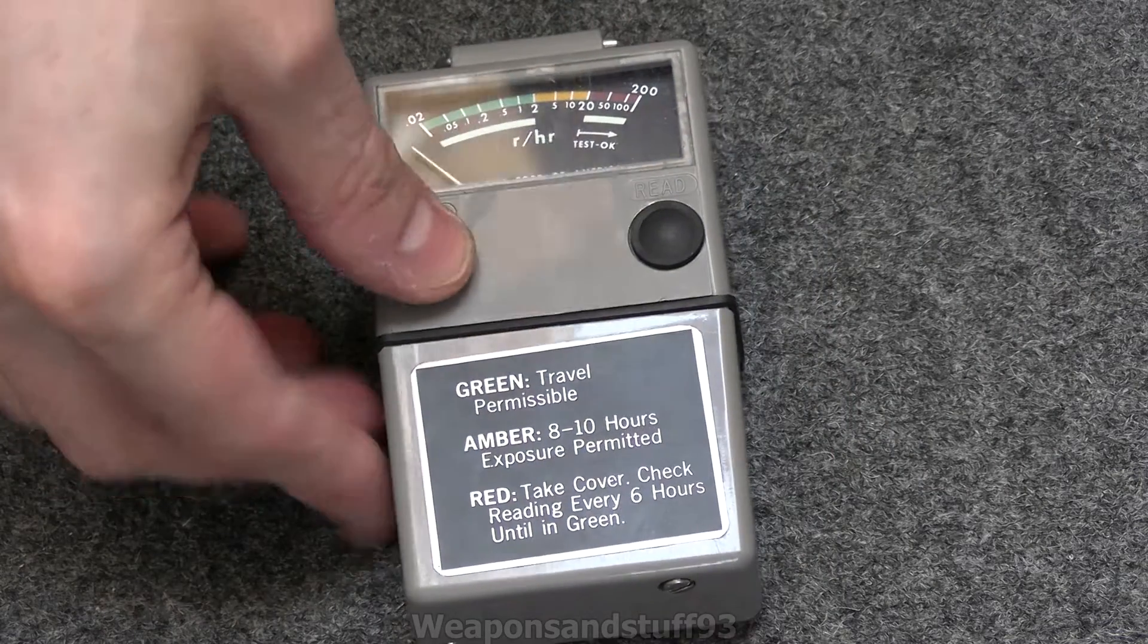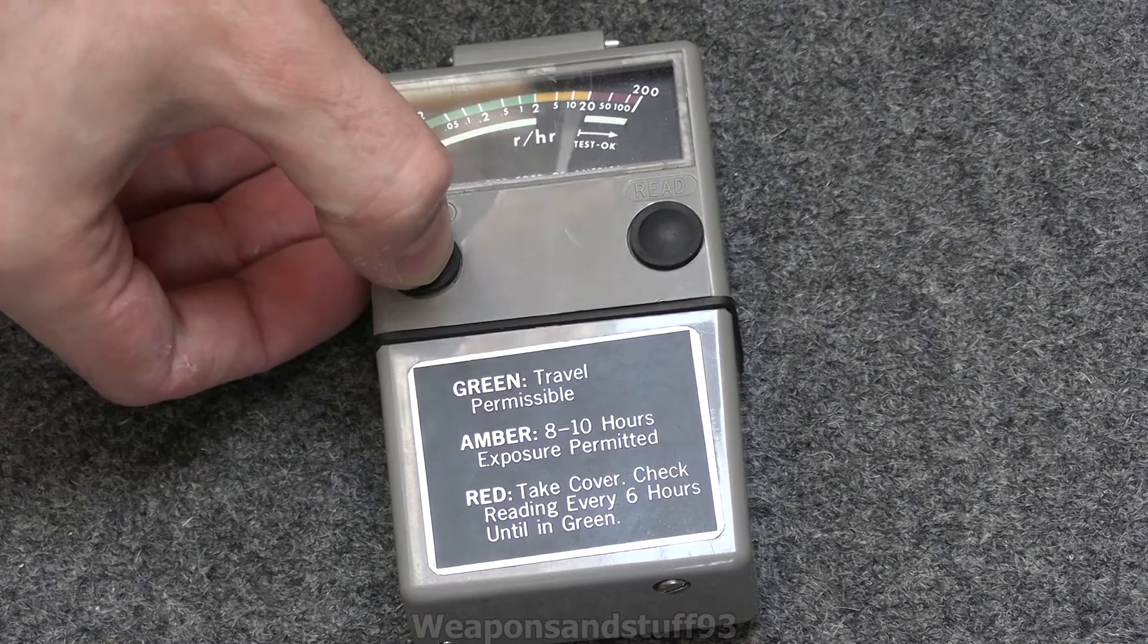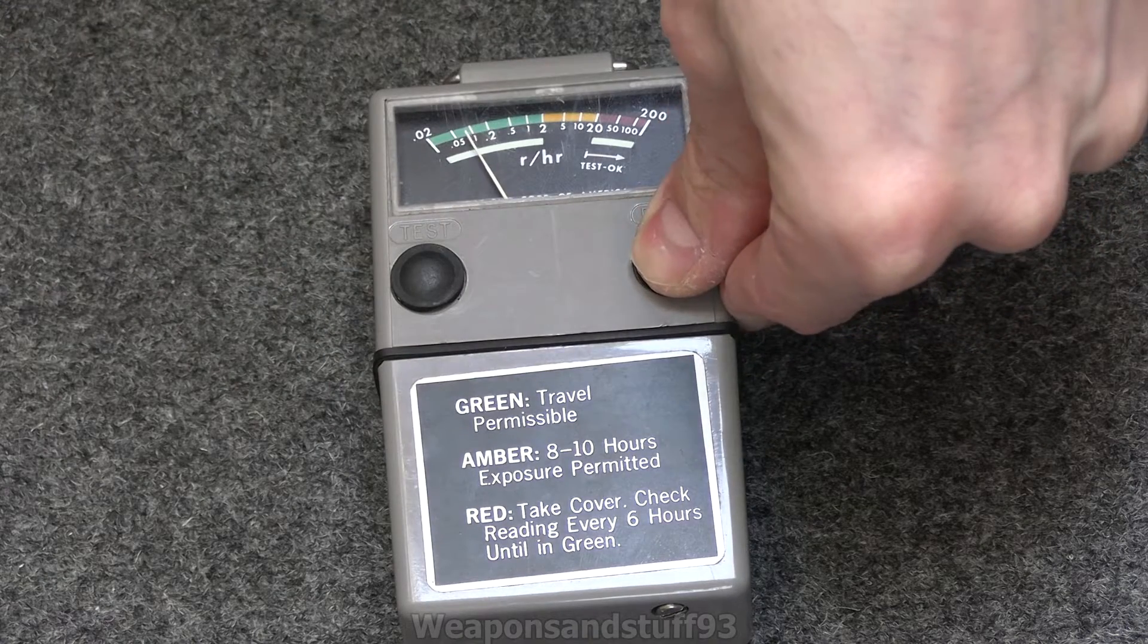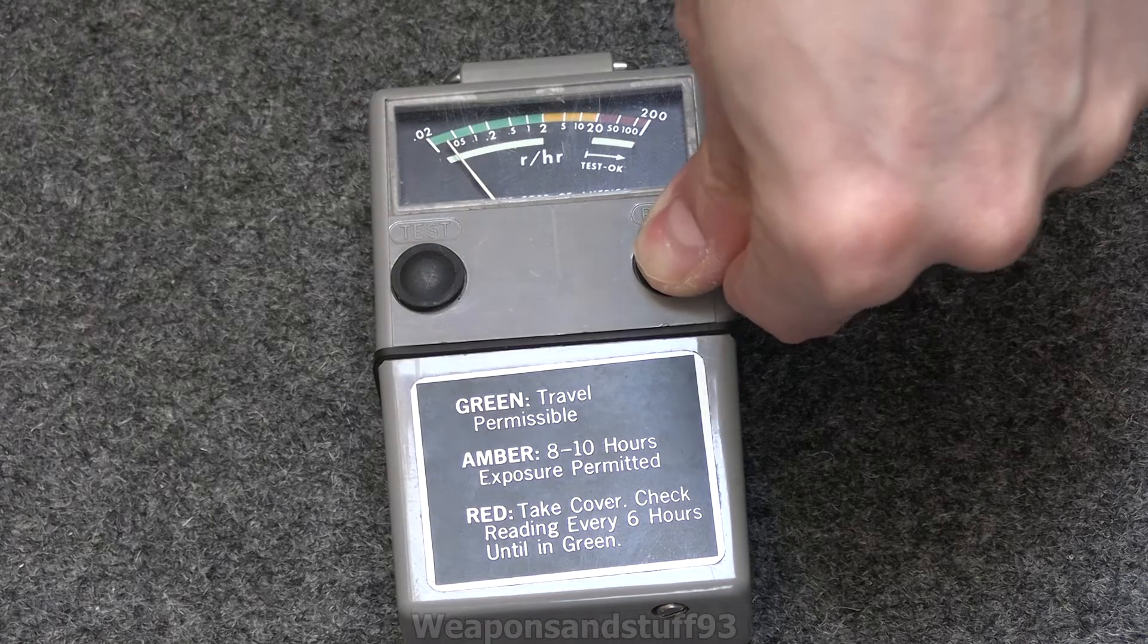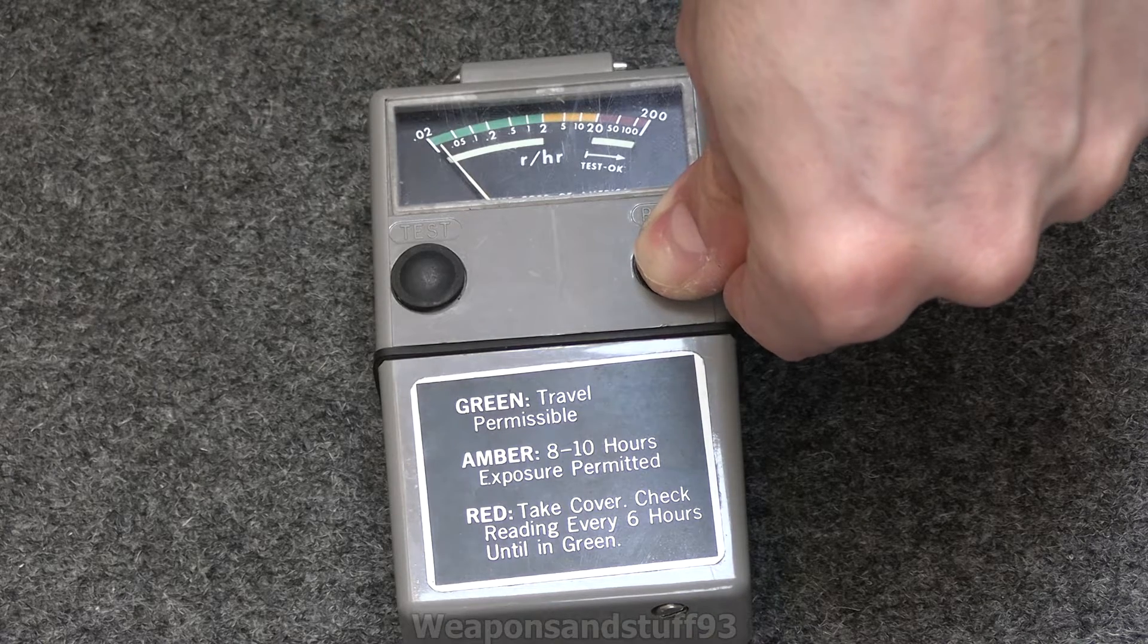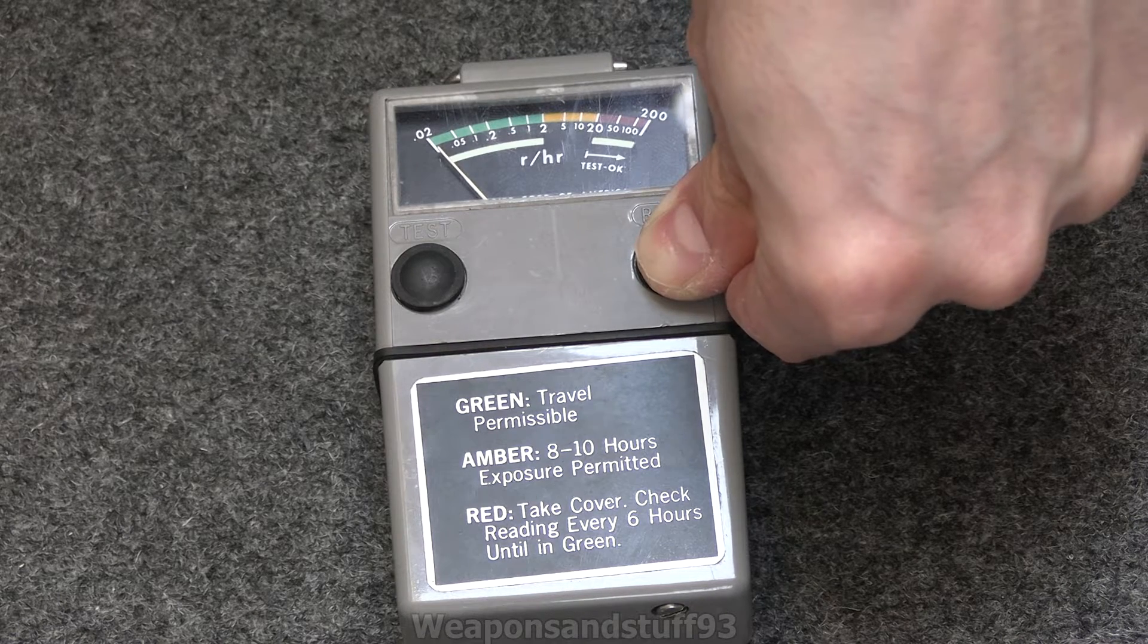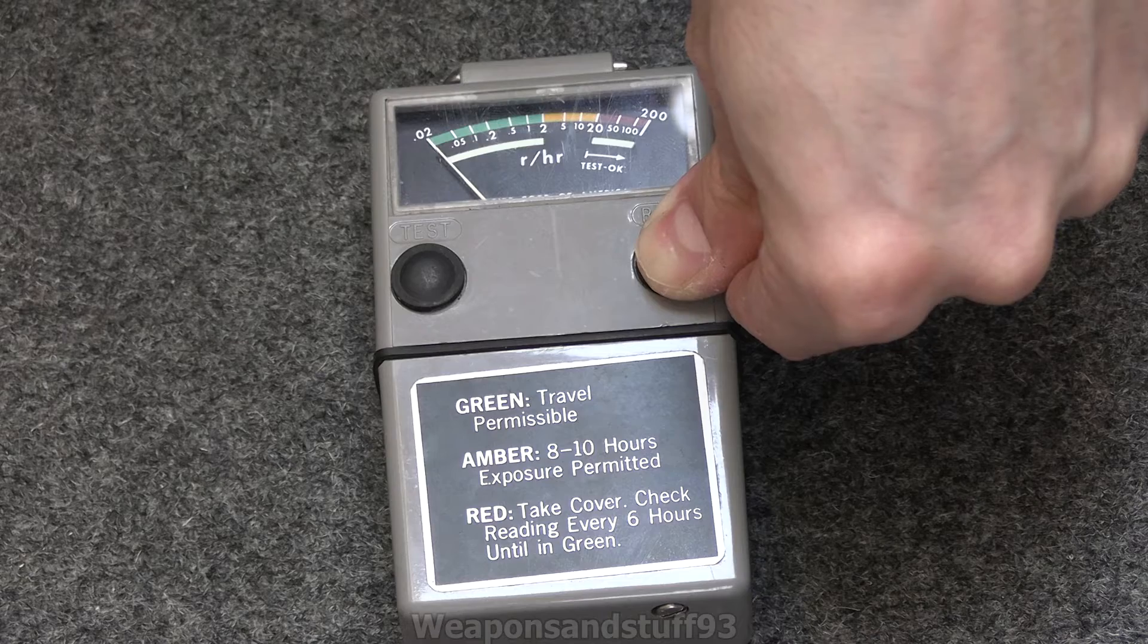There's a test function which basically just short circuits the device to check that all the electrics work, which is pretty standard of ion chambers. Then you've got your read button, that's the more interesting one. That powers up the ionization chamber, you hold it down for a few seconds before you're meant to take the reading because it needs to stabilize the voltage. What should happen is that the needle should end pretty much at the bottom of the reading range, and then once you start exposing it to radiation while holding it down, the needle should go up. That's all in theory. We're going to test it in a minute and see if we can get a reading to work on it.